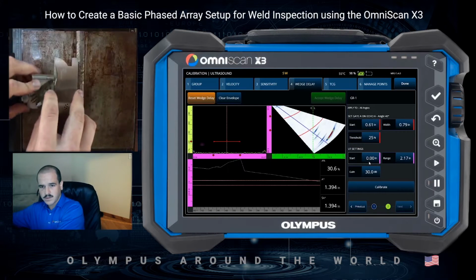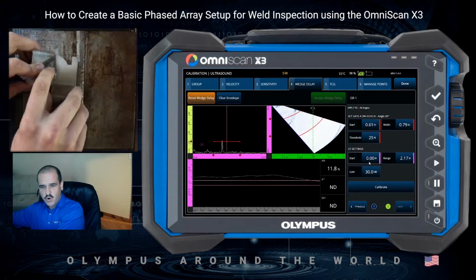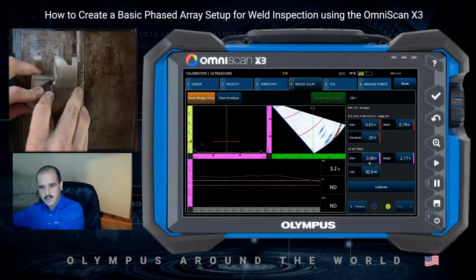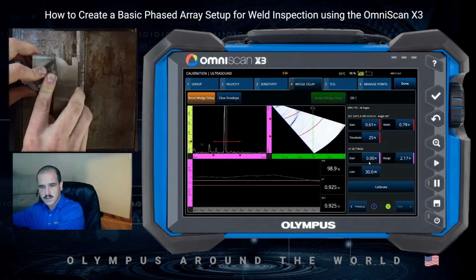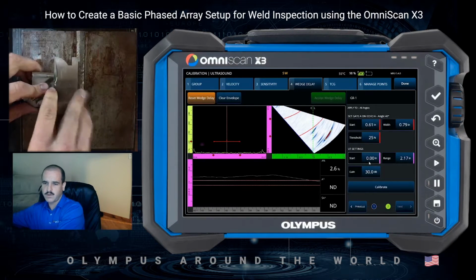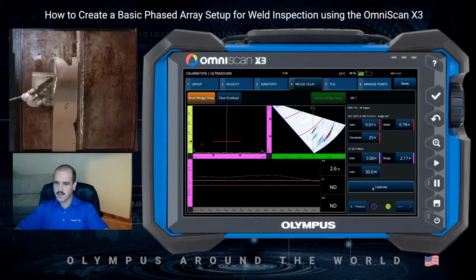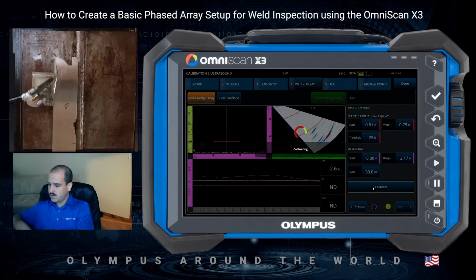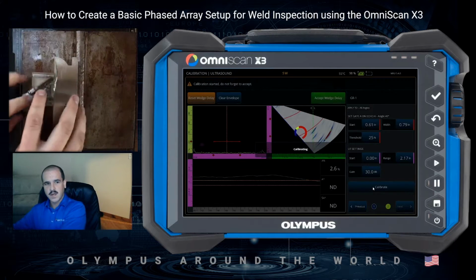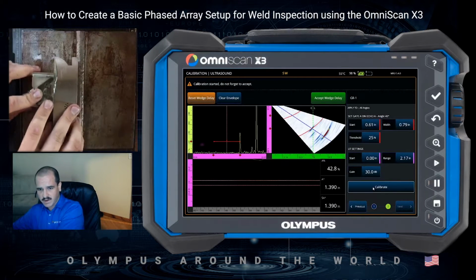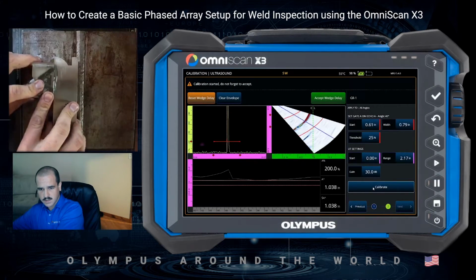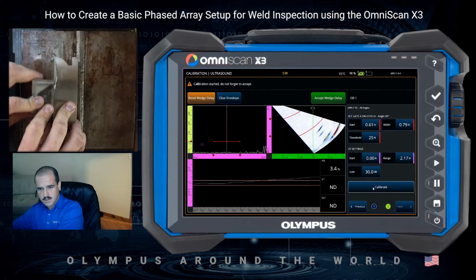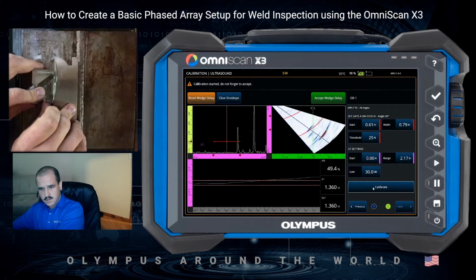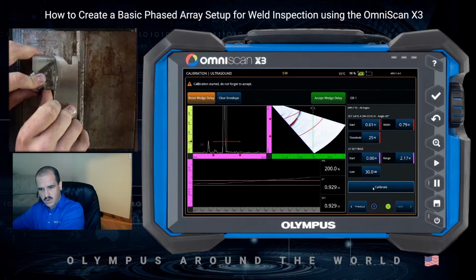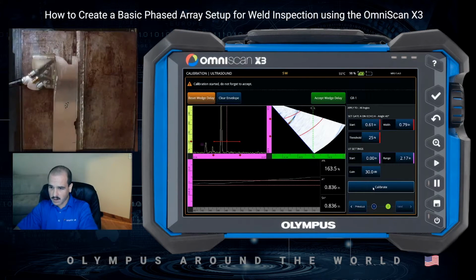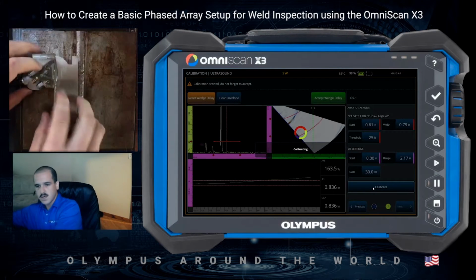So I'm just going to raster my probe across this radius. Try to peak it out across all the focal laws, and we'll select calibrate. Once the calibration is done, we'll raster it across again to verify our wedge delay. So we'll give it one more go here to try to get our higher angles a little bit closer to that tolerance.